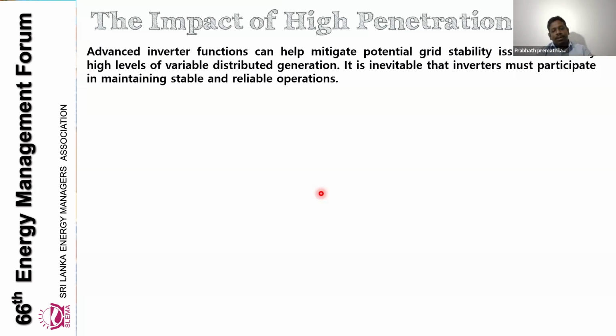That can be a challenge, but with the challenge, that can be a part of a solution. So what we need here is to get the support. We have to get involved whatever inverters are in our network. As I have shown you, around 1,750 megawatts of solar PV inverter capacity is in our network. If they can provide the support for the stability issue and voltage issues, yes, we have to take it.